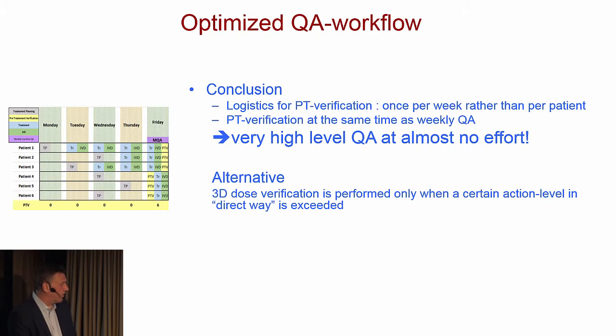Well, there is also an alternative, and that is that the 3D dose verification is performed only when a certain action level is exceeded in the direct way. So you know that many times when you run a pre-treatment verification on a patient, it's a pass directly. And if you would run the direct way and you set your action level in a decent way, then you will see that most of the patients will not require a pre-treatment verification, a calibration at all. So then you can skip that step, maybe. It's up to you to decide.